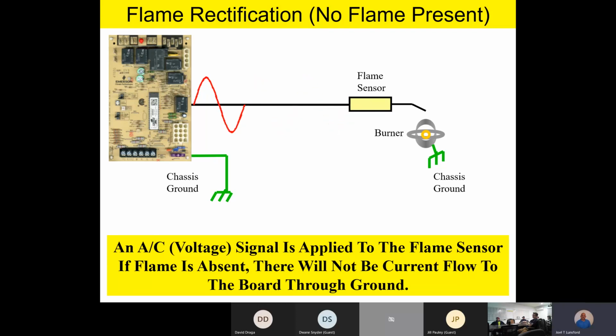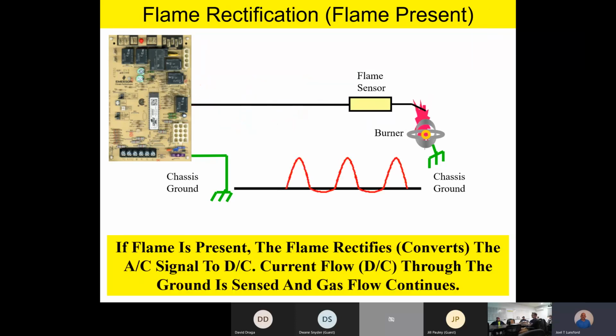Now, if a flame is absent, if we have no flame, nothing's going to happen. There's not going to be any current flow. But watch this. As soon as you have flame on the burner, that AC voltage is going to go through the flame, down to chassis ground, and back to the board. And so the flame actually rectifies or converts that AC voltage to a DC voltage. Now that DC is going to be sensed on the ground plane, and then gas will continue to flow to the burner.